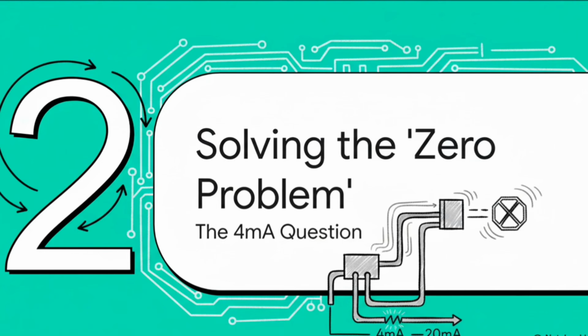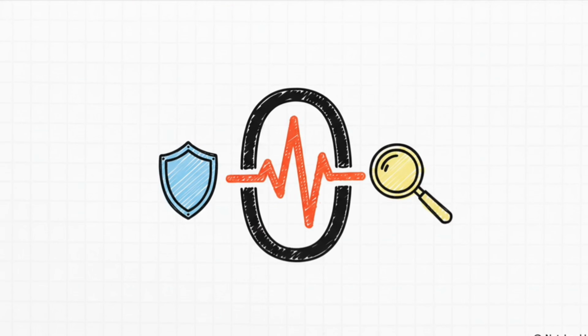Okay, so now we get to the core of it. We have the background. Let's solve this 0 problem and really understand the genius behind starting at 4 milliamps instead of 0. And the answer? The entire reason boils down to one brilliant, elegant concept. It's called live zero. And trust me, this isn't just some random technical detail, it's a critical safety and diagnostic feature that's baked right into the standard.